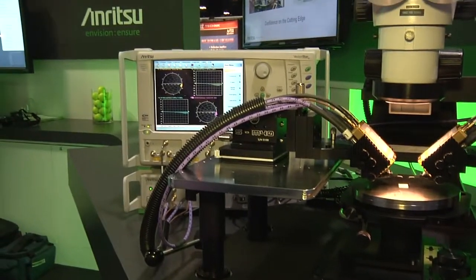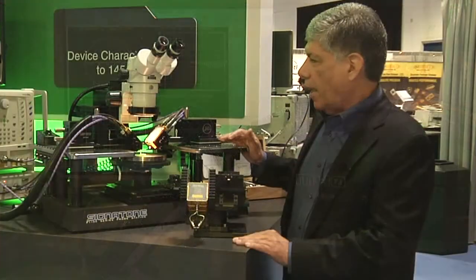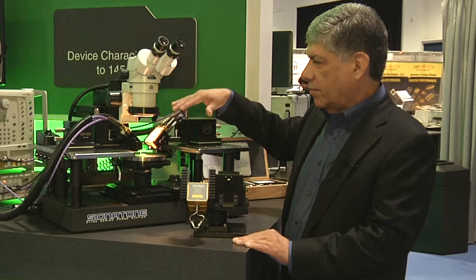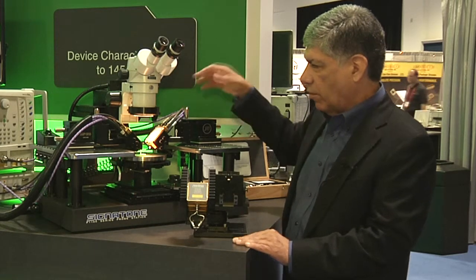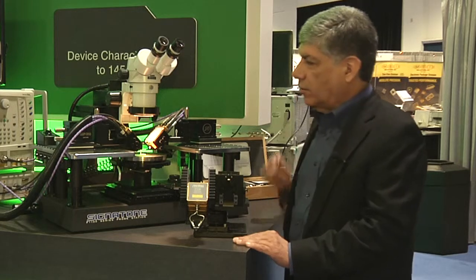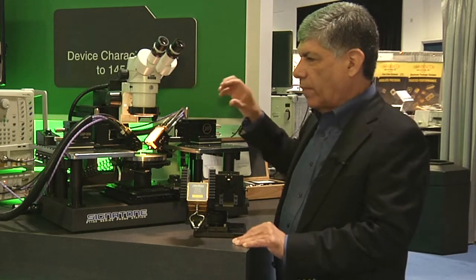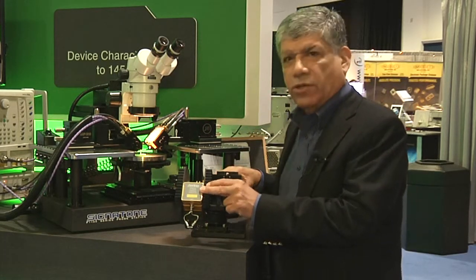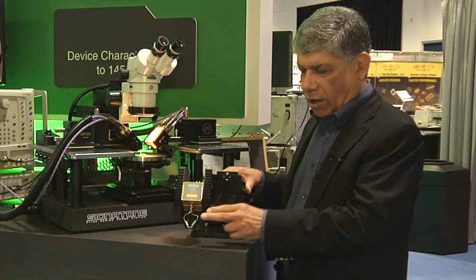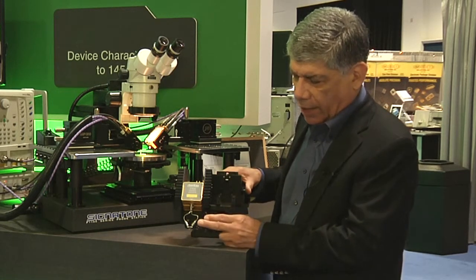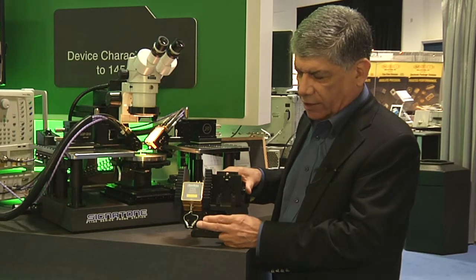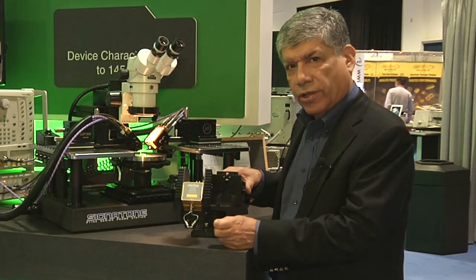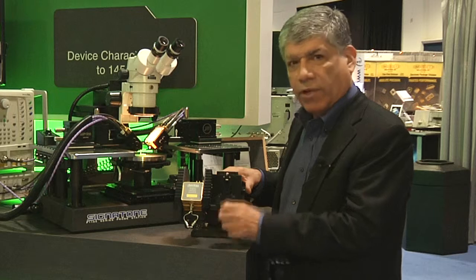And we're also mounted on a probe station. This one's from Signatone. And you can see that the small compact size makes it quite easy to mount the system in any configuration, whether it's east-west or north-south. And also, when you're looking at the modules for going into differential types of measurements, you can see that it's quite easy to mount two modules on the positioners and make it such that the connections from the probe to the modules are quite short. So that also maximizes your dynamic range.